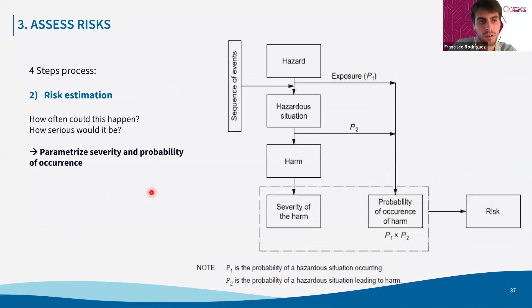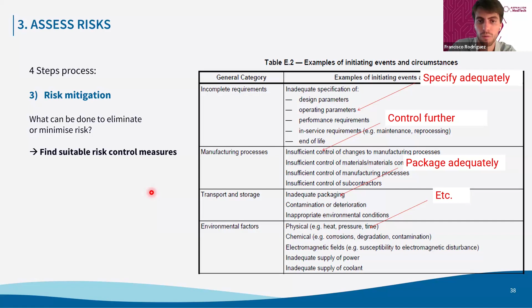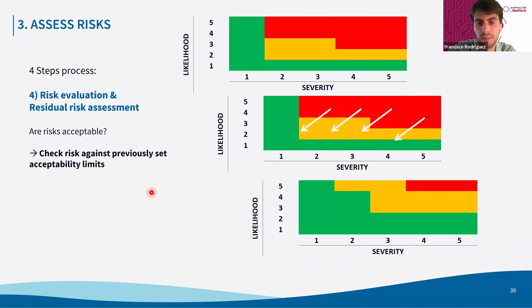This mitigating measure could be a change of the design, which will be the most powerful mitigating measure, or maybe this mitigating measure could be, for example, including a warning or a disclaimer within the instructions for use so that our intended users are aware of these potential risks and we avoid them as far as possible. At the end, as I said before, the idea is that we move all of our risks to a safe area and we have reduced them as far as possible.